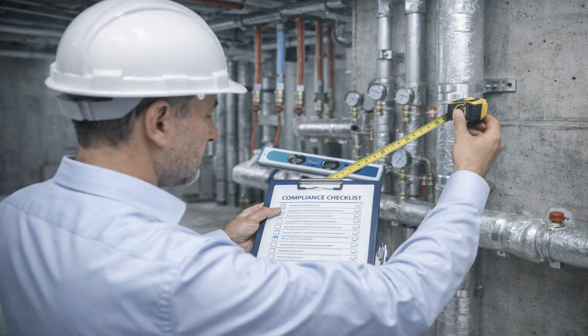Common issues include incomplete or rushed pressure tests, improper flushing leading to debris and long-term system damage, and poor insulation installation causing condensation and energy loss. British standards remove ambiguity. They clearly define how testing should be done and what acceptable looks like. So when a contractor says, this is how we usually do it, inspectors respond with, show compliance with applicable British standards. In short, design gets you approval, execution gets you accepted. And British standards sit right at the center of this process, ensuring systems are not just installed but tested, commissioned, and handed over correctly. Now let's shift focus from site execution to equipment itself.